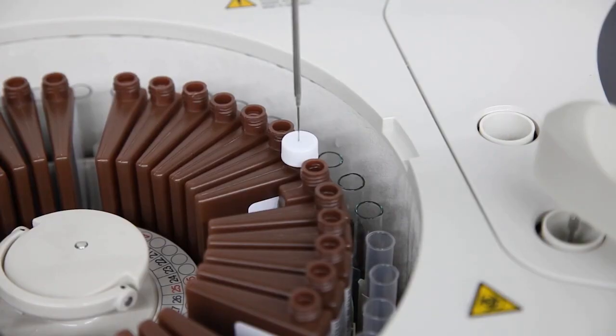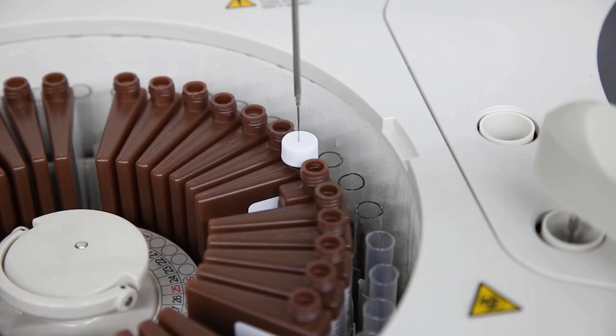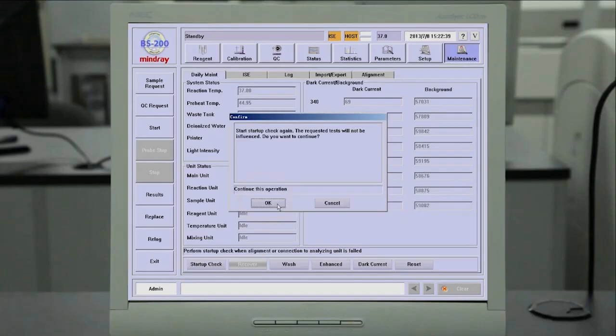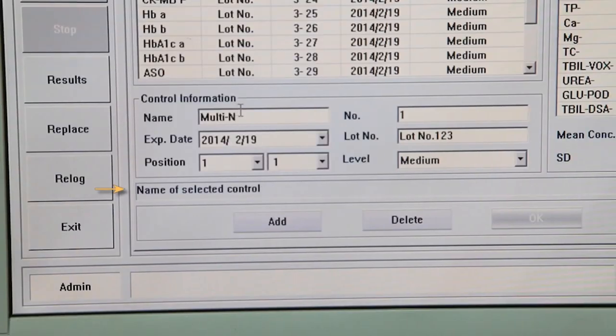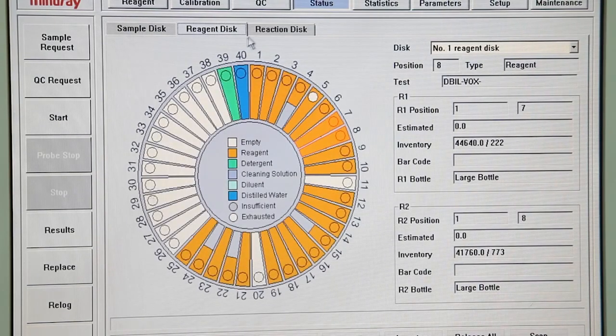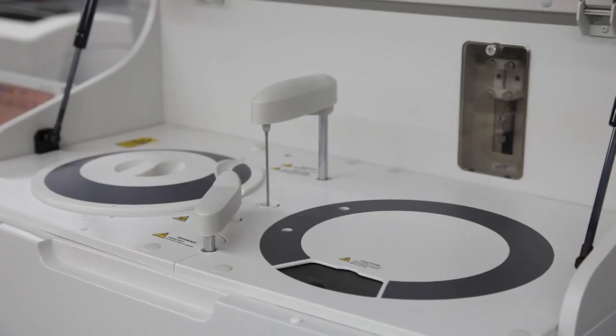Should a probe collision ever happen, the analyzer gives an alarm and stops after trying three times. The operator simply removes the obstruction or resets the instrument with a simple one-touch recovery button. The software is intuitive and easy to use with written instructions indicated from each field. Simply move the cursor to the desired field and follow the display instructions. During testing, the operator may monitor the real-time status of the reactions, the reagent, and the sample carousels from the colorful screen display. Once all samples are programmed and loaded on board, the operator may enjoy an hour of walk-away time to perform other laboratory functions.